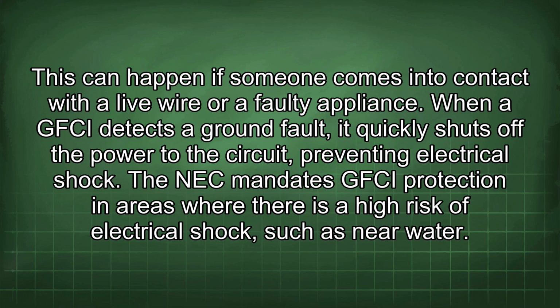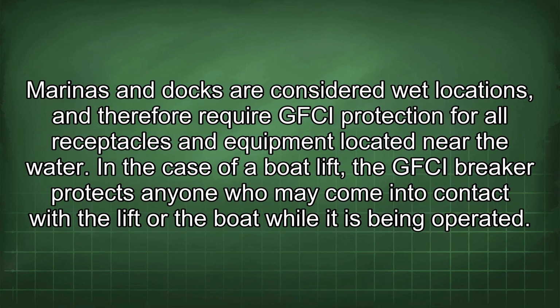The NEC mandates GFCI protection in areas where there is a high risk of electrical shock, such as near water. Marinas and docks are considered wet locations, and therefore require GFCI protection for all receptacles and equipment located near the water. In the case of a boat lift, the GFCI breaker protects anyone who may come into contact with the lift or the boat while it is being operated.